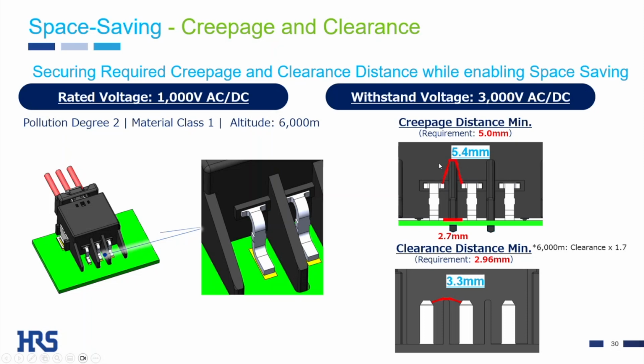Altitude also increased the required clearance. Within its scope of pollution degree 2, material class 1, and altitude of 6,000 meters, the requirements are 5 mm creepage and 2.96 mm clearance, and ZE150HV provides 5.4 and 3.3 mm, so there is genuine margin on both. The selling message is short: safe, and compact by design.